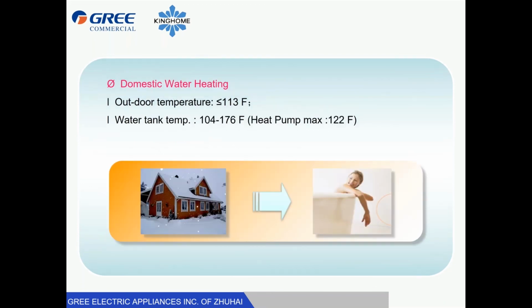And we can also do domestic hot water. So you will likely want to use an auxiliary heat for your hot water tank because we can't do simultaneous heating and cooling. So for example, if you have a summertime condition where the air conditioner is running, but someone wants to run the hot water, we can set hot water priority in the controller. So it will switch from generating cold water to generating hot water to maintain the hot water heat for the domestic hot water system. And then it'll switch back to cooling mode for the fan coil.